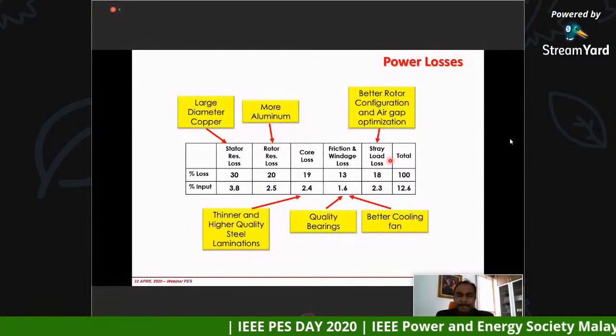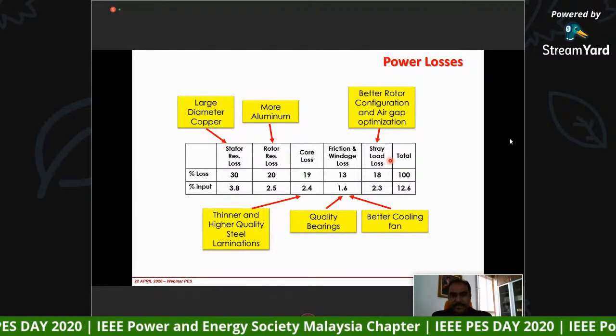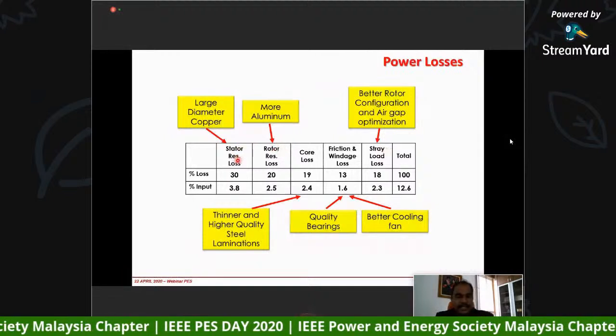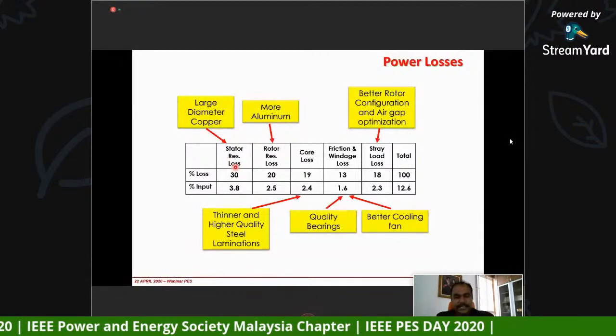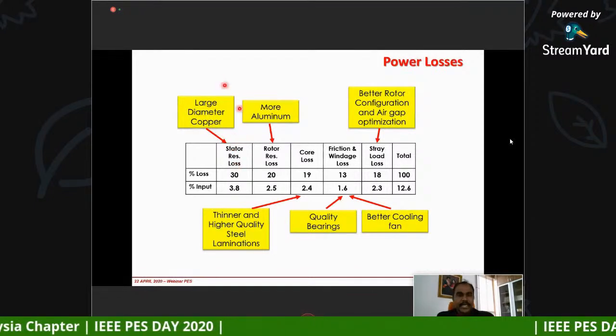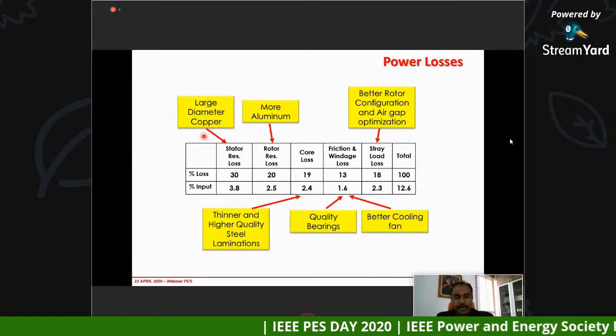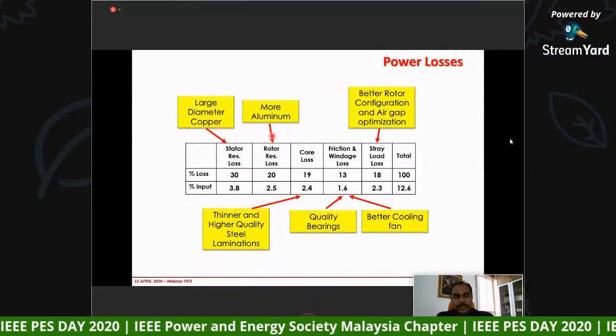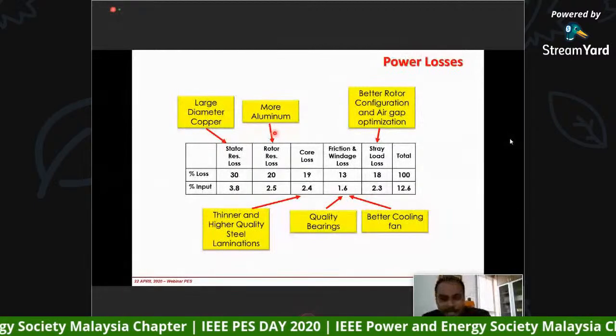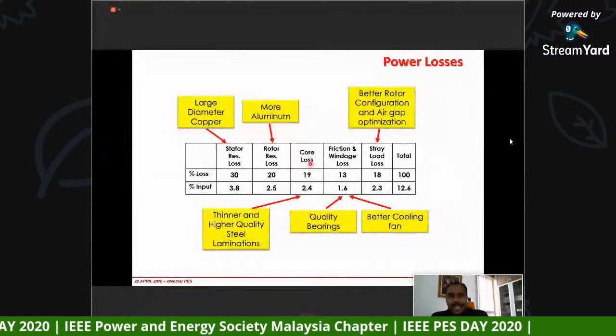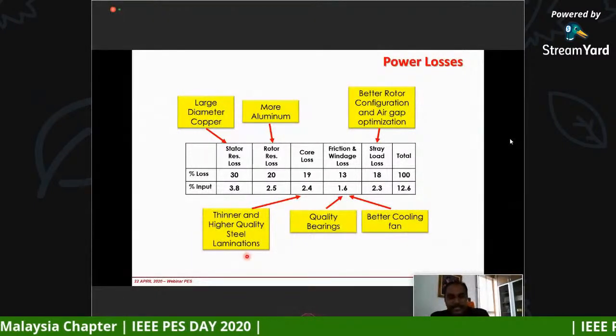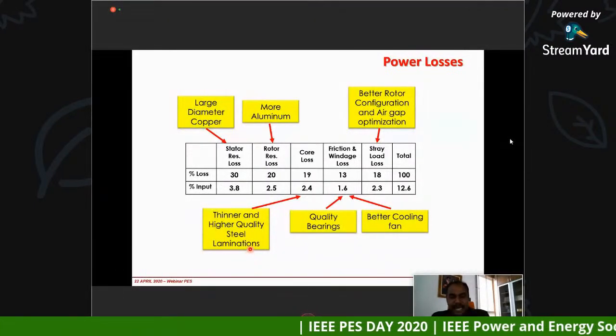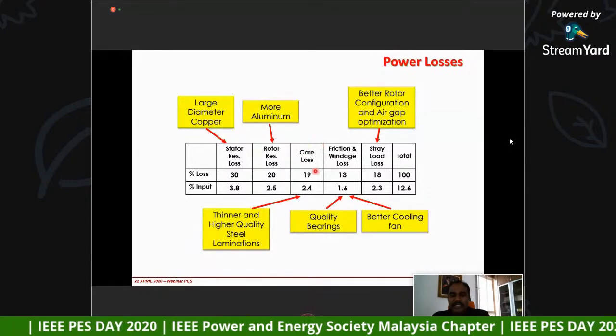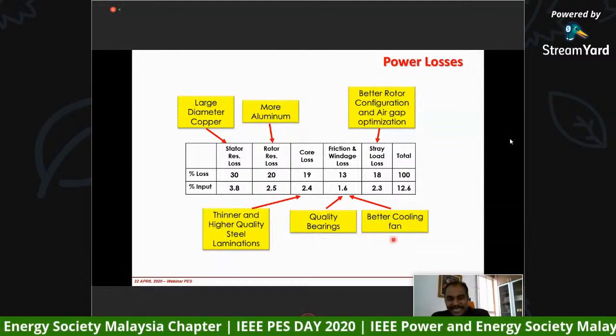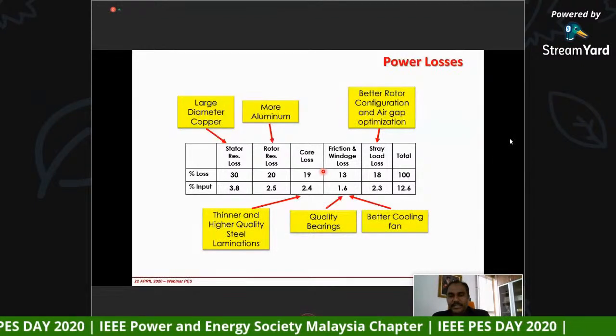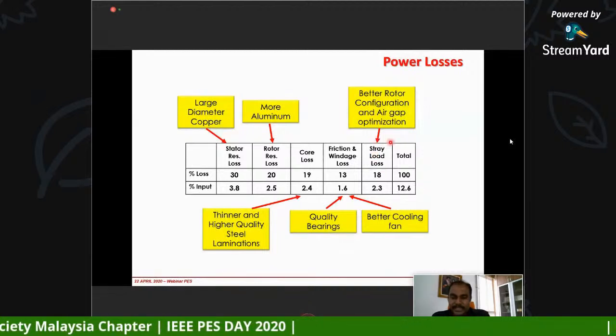So what happened is the existing induction motor, they optimize it. How do they optimize? For instance, if you're talking about reducing the resistance losses in the stator winding, they use a larger diameter copper as a winding, as a coil. Similarly, more aluminum at the rotor. All this will minimize the resistance, and therefore reduce the losses. And for the core loss, of course, they use a better quality steel lamination, thinner and high quality steel, to minimize the core loss. Similarly, better quality bearings and a better cooling fan, which reduce the friction and windage losses. Similarly, they optimize the air gap to reduce the stray load losses.